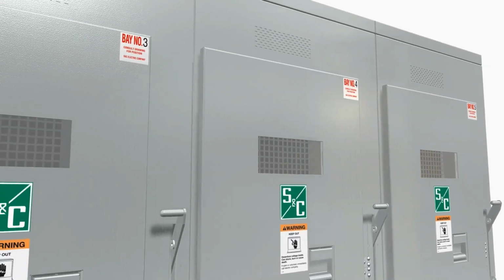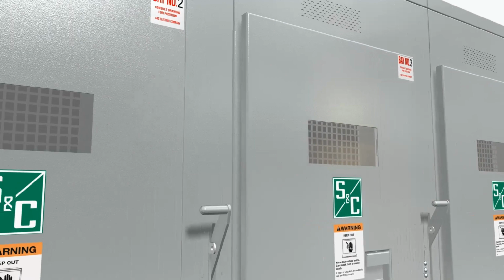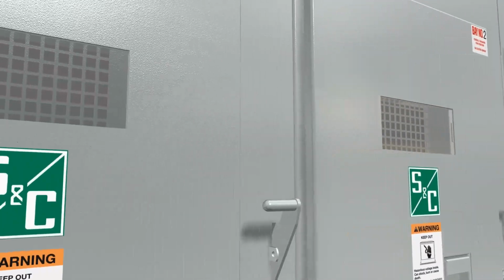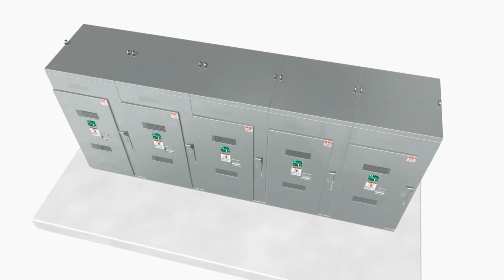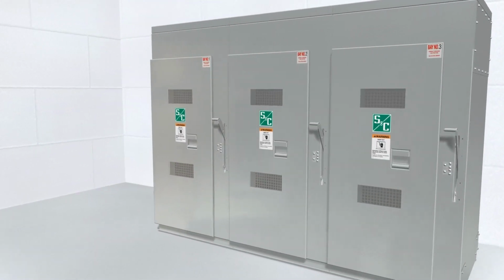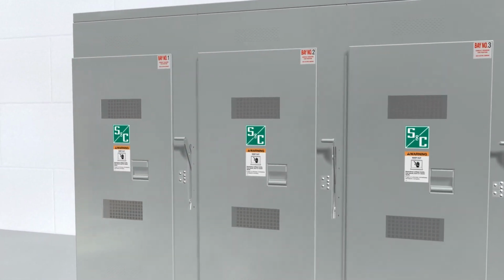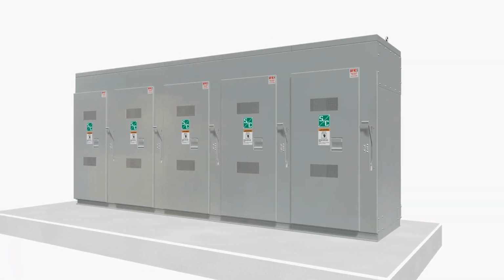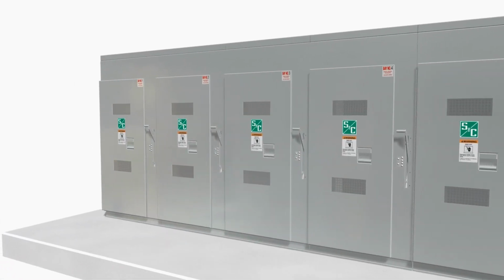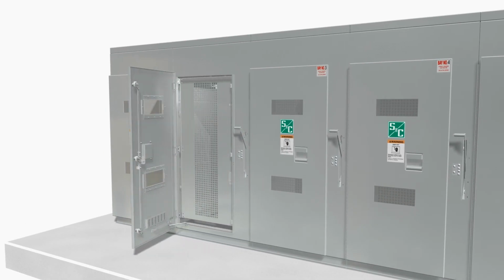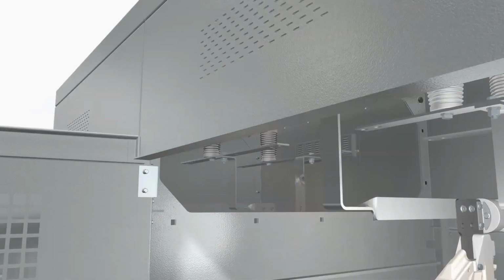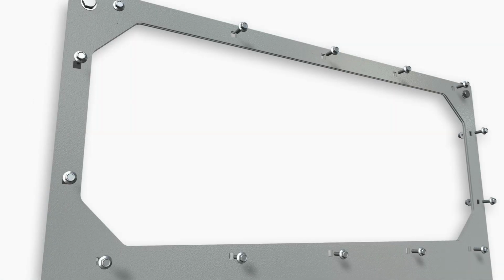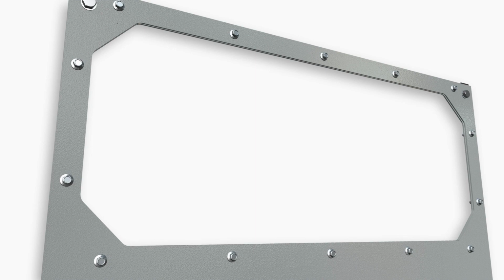Step 6. For switchgear rated 4.16 kV or 13.8 kV, on outdoor switchgear, as well as indoor switchgear with optional dustproof or drip-proof construction, after all bays are in place and bolted together, sides and top edges of through bus openings between bays should have the supplied extruded rubber channel gasket installed. A. To facilitate installation of the channel gasket, install and tighten bolts and nuts at the edges of the through bus openings on adjacent bays using the 5/16" hardware provided.